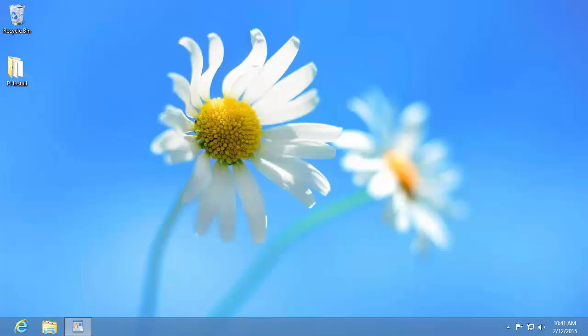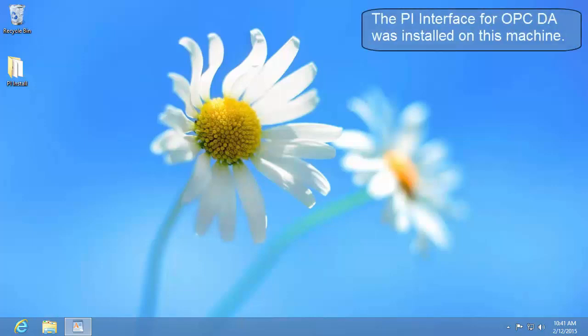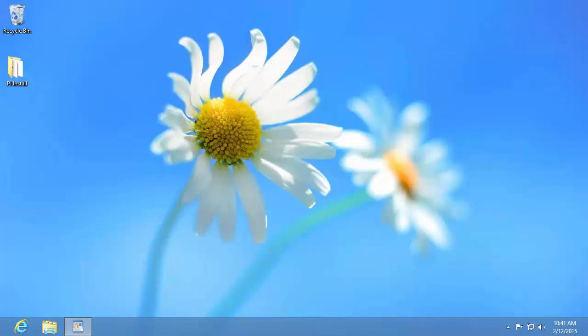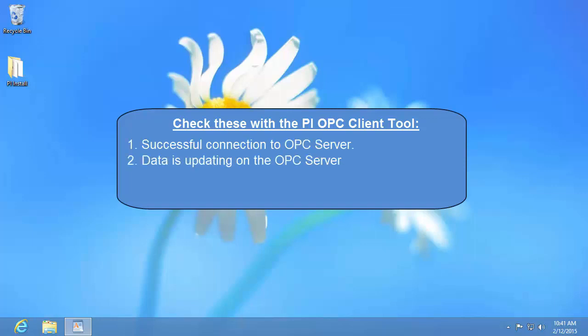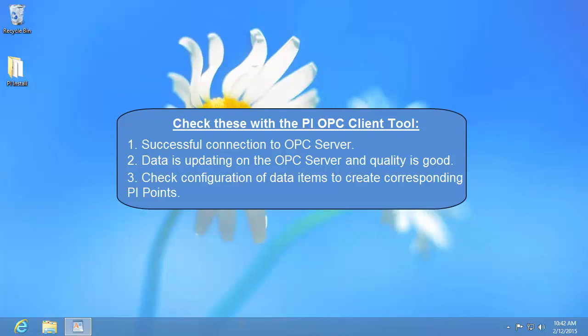In this video I'm going to show you how to connect to an OPC server and browse for data using the PI OPC client tool. Right now we're at the point where we have installed the PI interface for OPC DA, but we haven't configured any instance of the interface yet. Before we configure anything, we're going to want to make sure that our PI interface is going to be able to connect to the OPC server and access data on it. We also want to make sure that that data is currently good, and we might want to choose which data we're going to be collecting. We can do all this using the PI OPC client tool, which is installed when you install the PI interface for OPC DA.